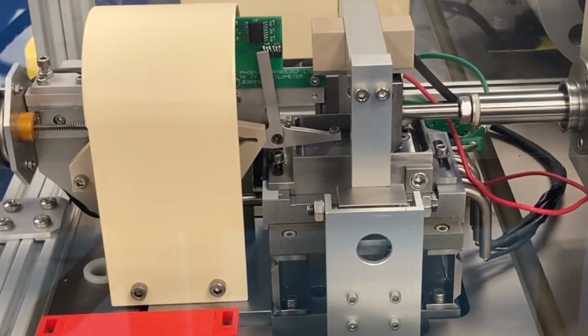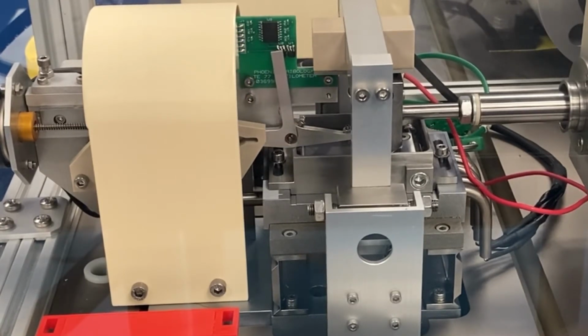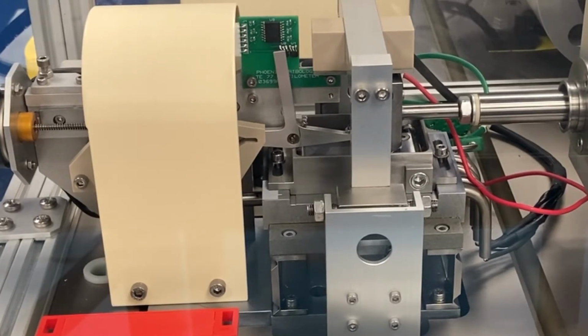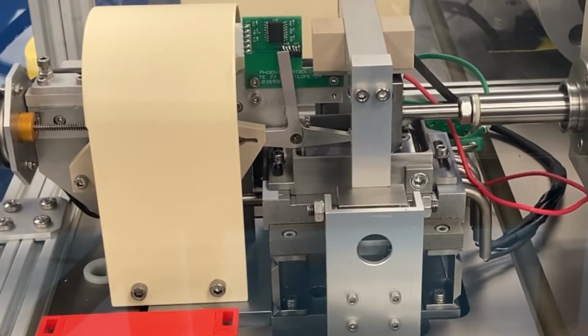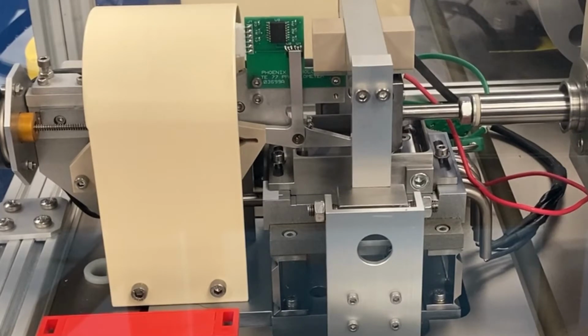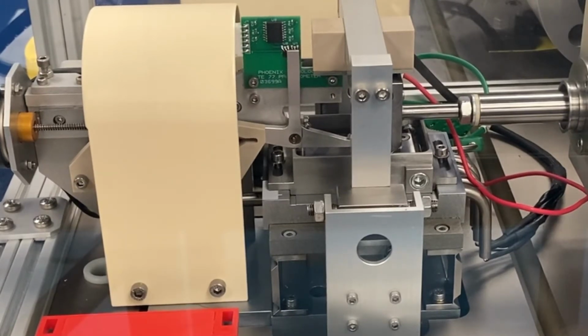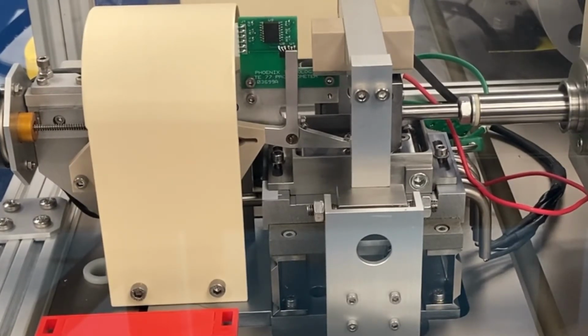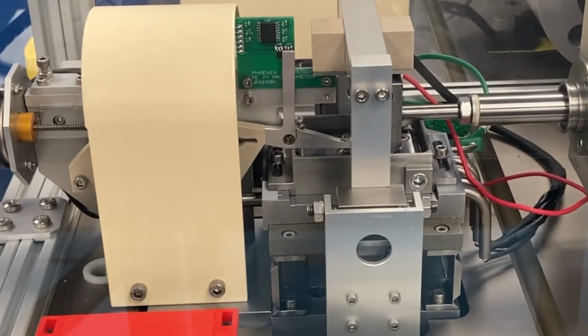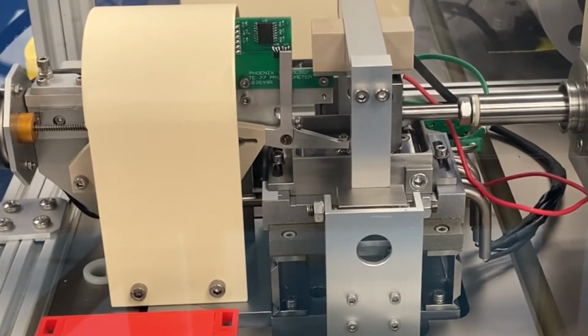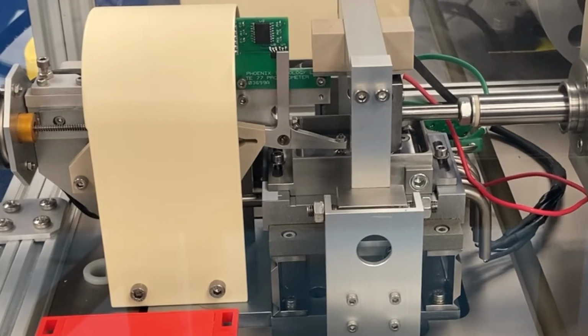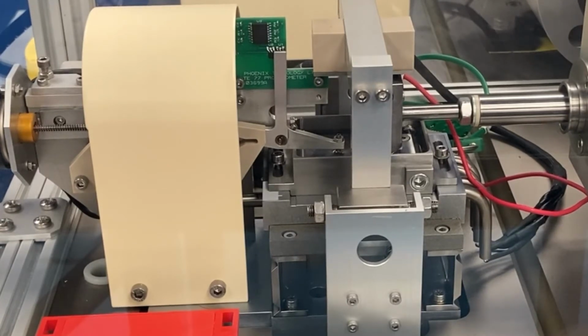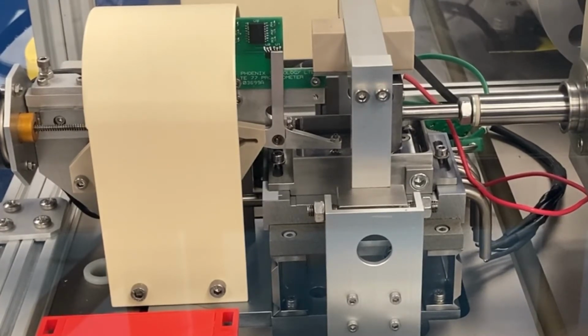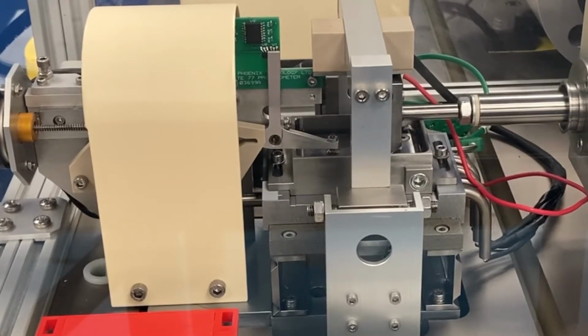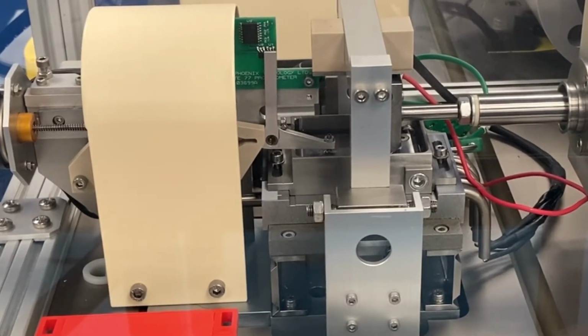Every test starts with the measurement of an unworn surface, which is used as the reference surface for subsequent measurements. Raw traces are processed by subtracting the reference surface profile from each subsequent profile. An average is calculated for each processed trace. This gives an unscaled measurement of the trace area proportional to the wear volume.